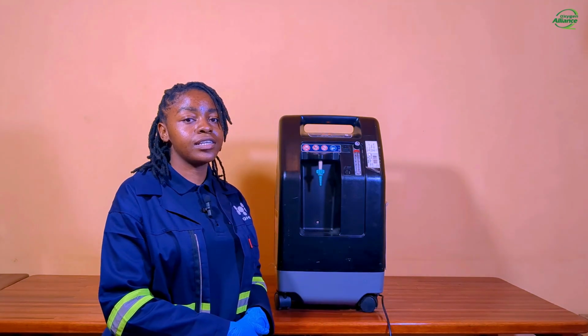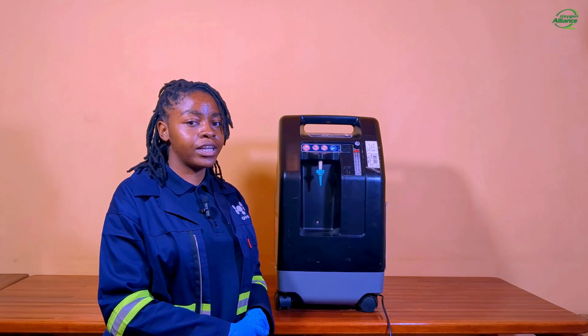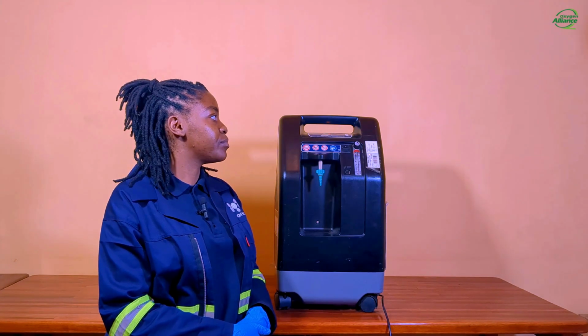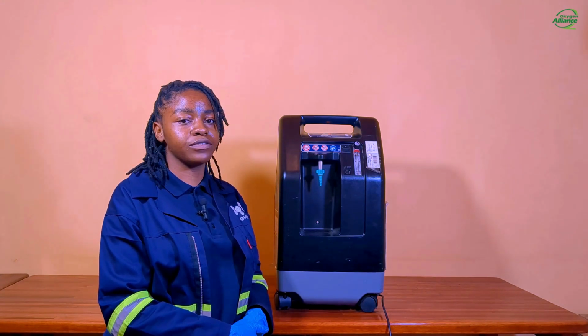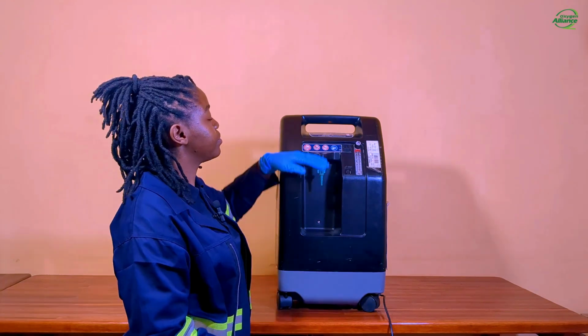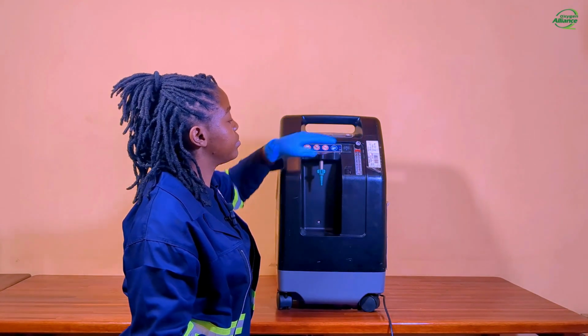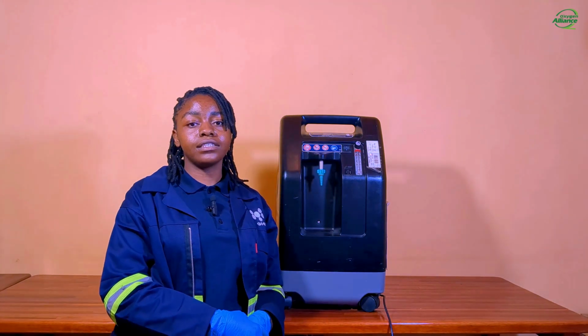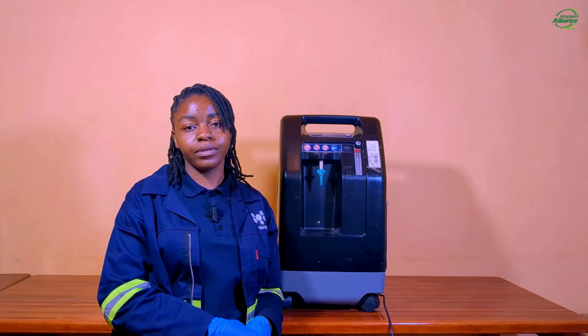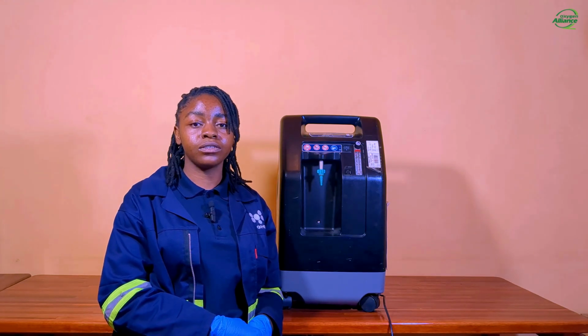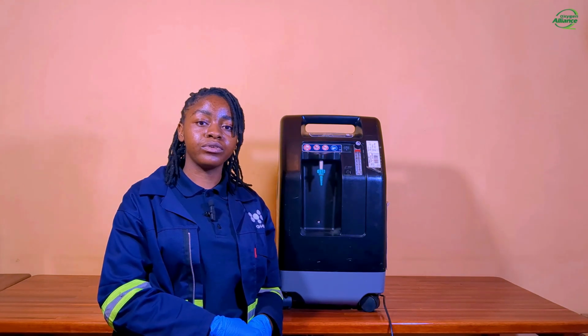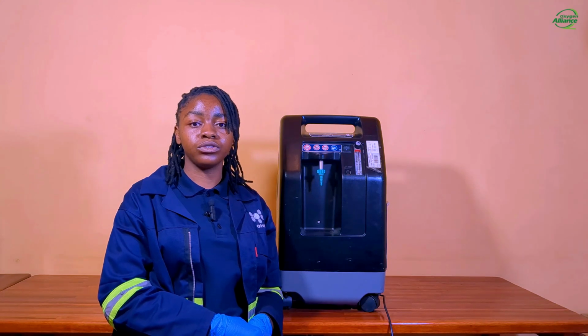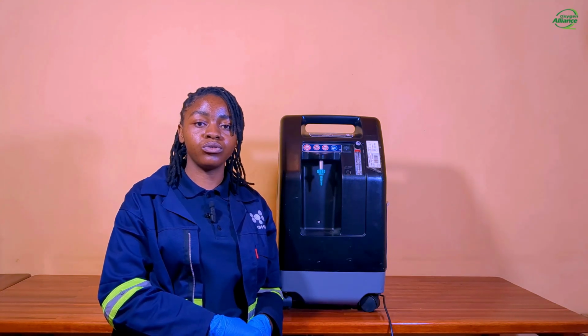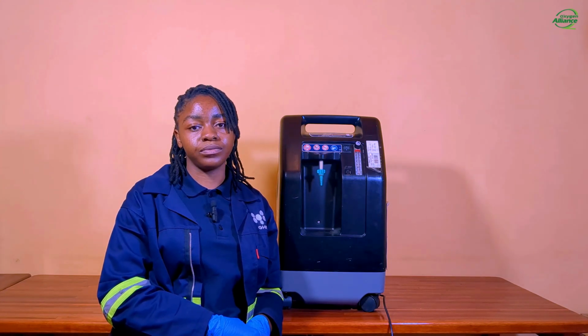So as you can see, the yellow light has turned on, which shows that the purity of oxygen has gone below 85%. This is accompanied by an audible alarm. And if the concentration goes below 60%, both the red and the yellow LED will turn on, showing that the concentration is too low and that the concentrator needs service.